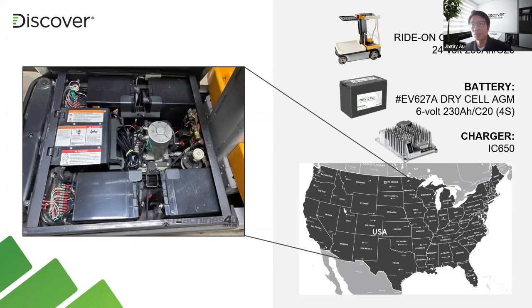In this particular setup, you can see the batteries are actually installed on their side and not upright. So the ideal choice, as you can see here, would be AGM. As we mentioned earlier, AGM batteries' electrolyte is not free flowing, not in liquid form, but rather suspended and absorbed in the glass mat material. So it's maintenance free, non-spillable, and fully sealed.